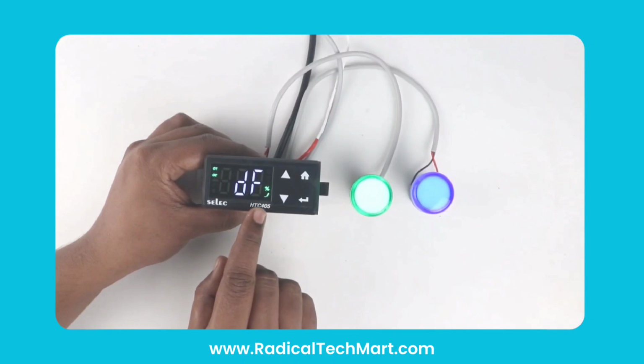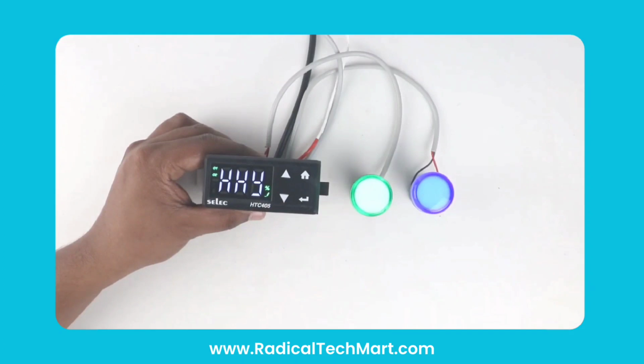Next is humidity hysteresis, which is set to 0.5 by default. You can adjust this between 0.1 and 99.9. This value is the difference between the relay turning on and off relative to the humidity set point.